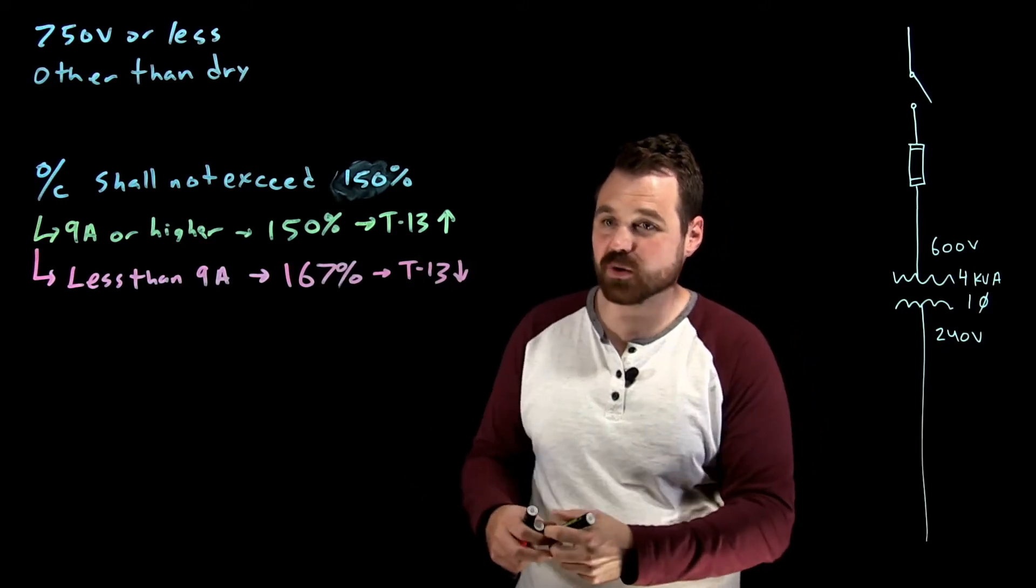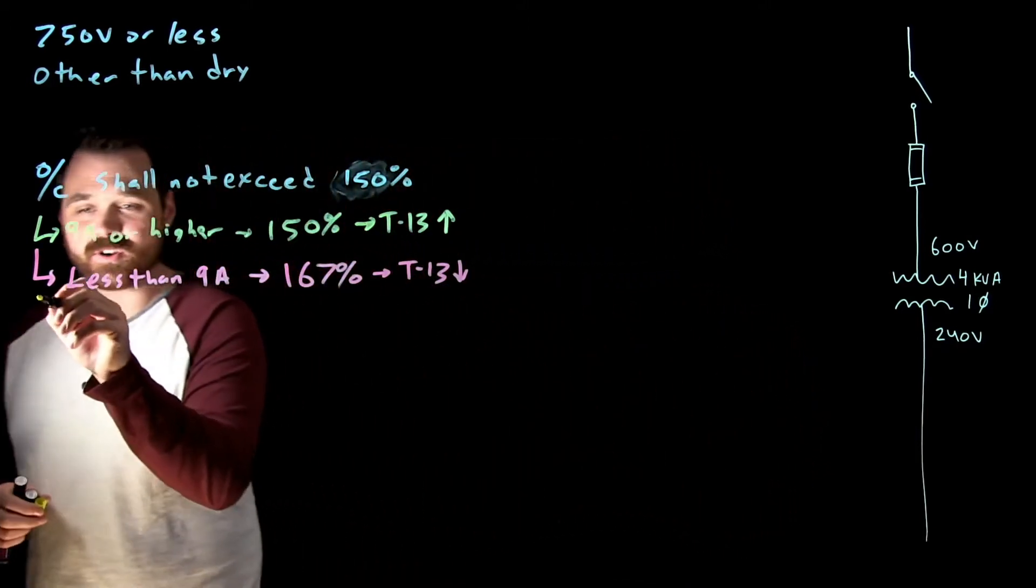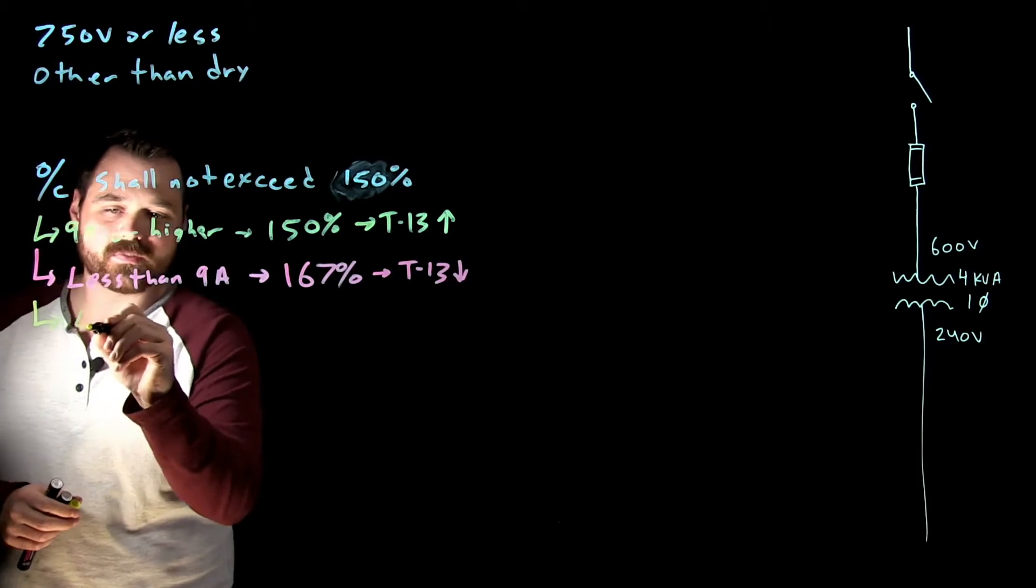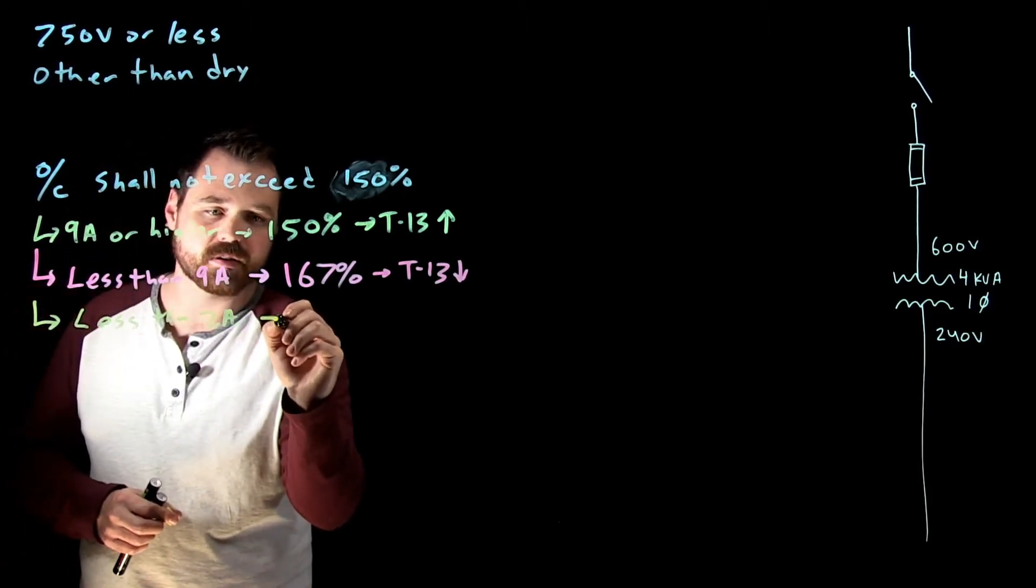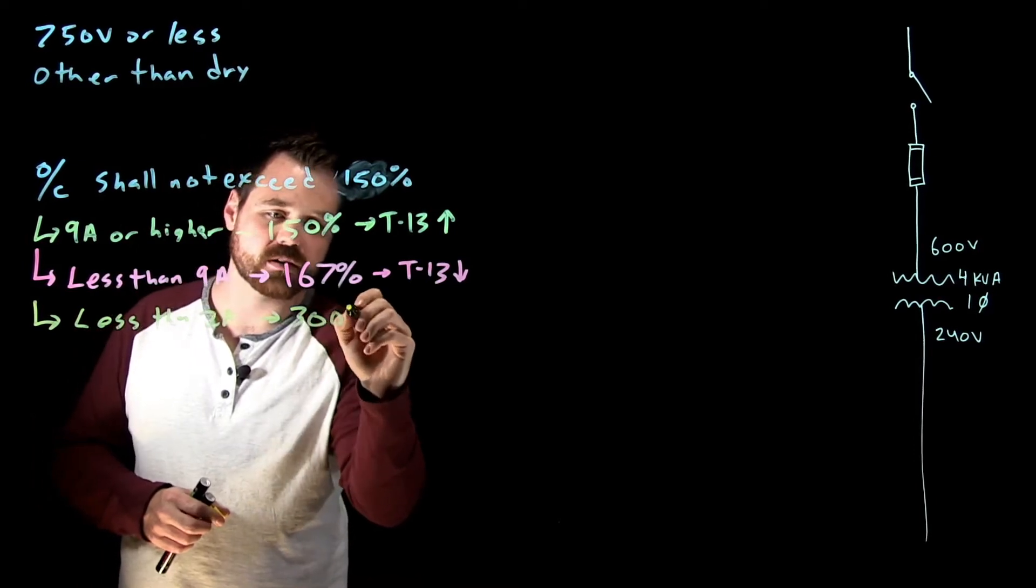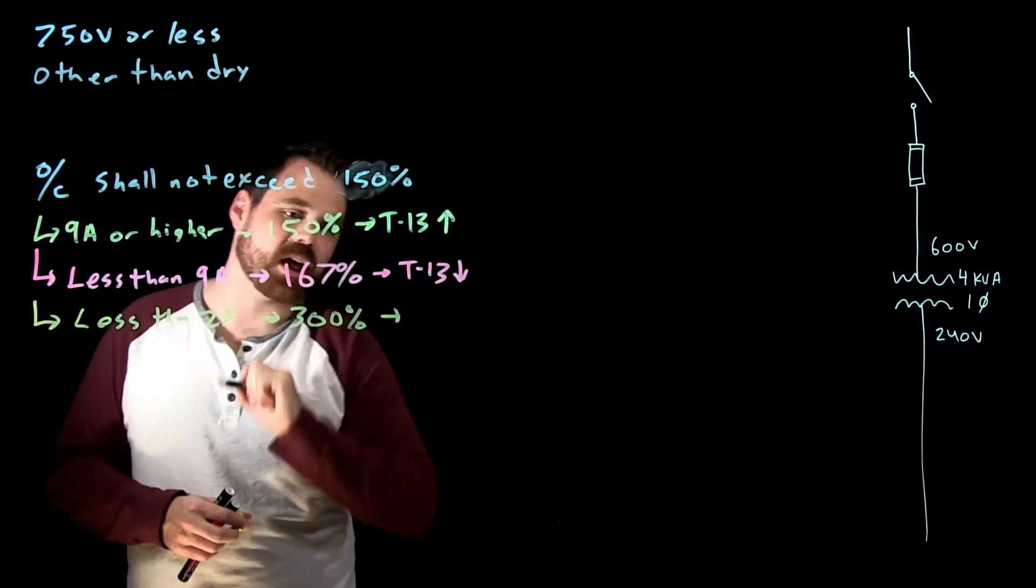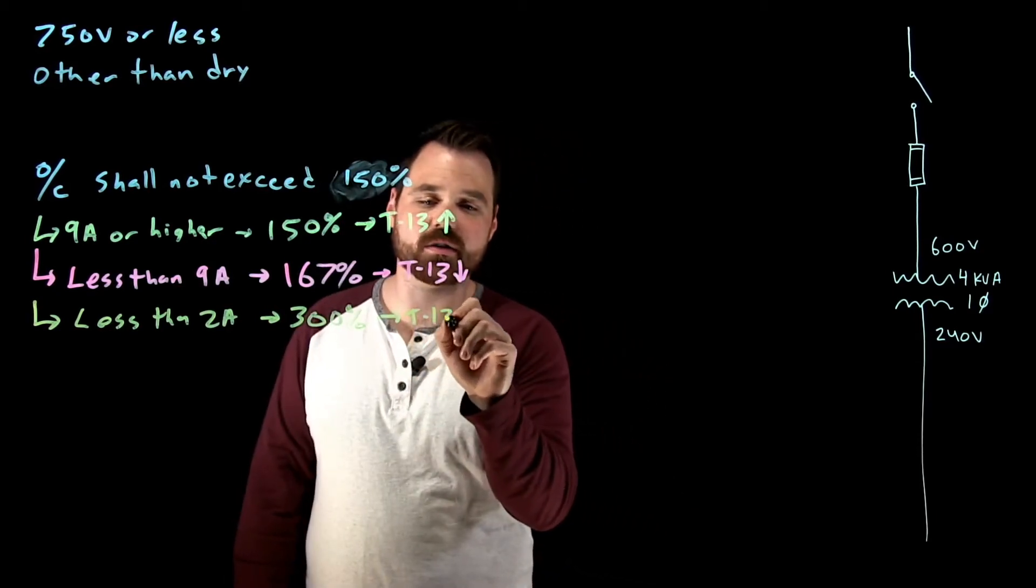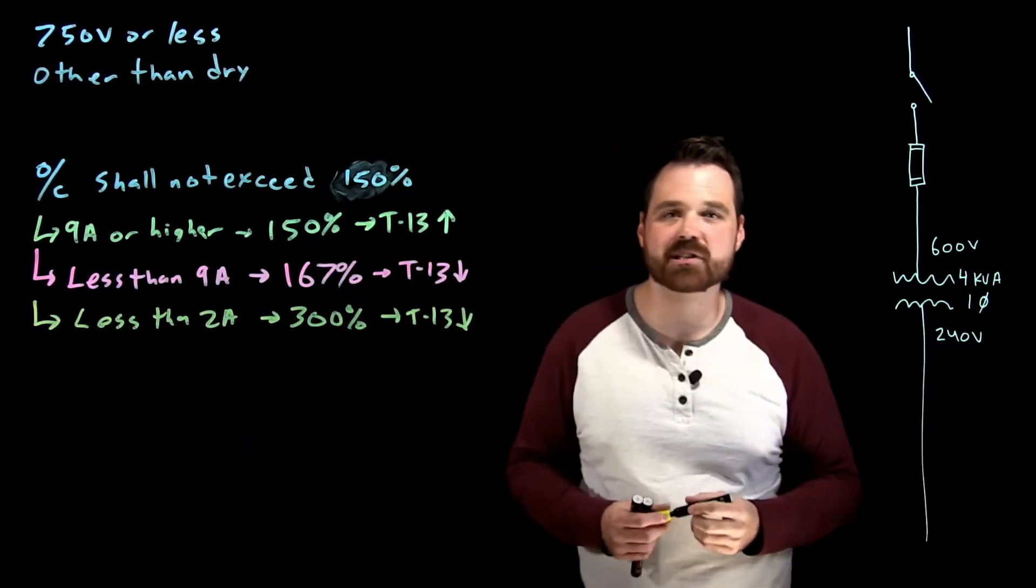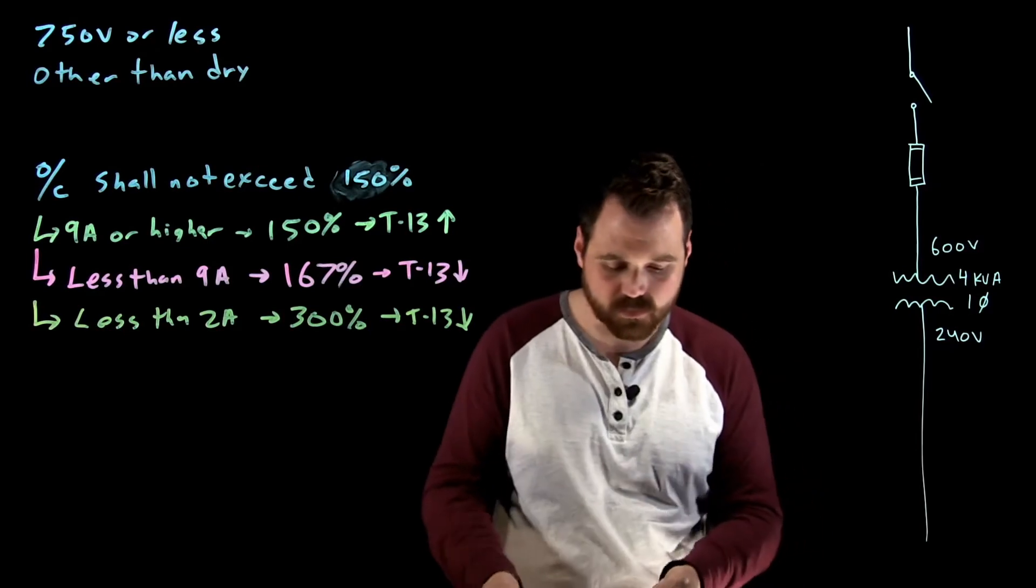Then the very last rule says if you're less than two amps, it's 300%. And if 300% isn't available when you're sizing your OC, you actually go down to the next smaller size, right?